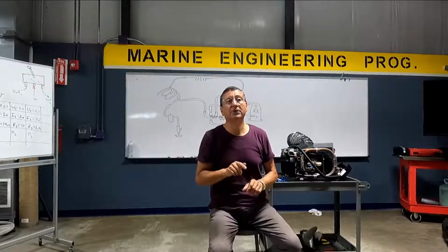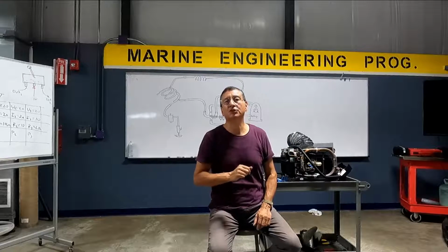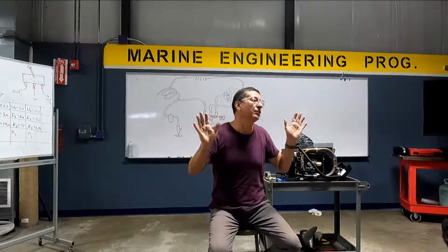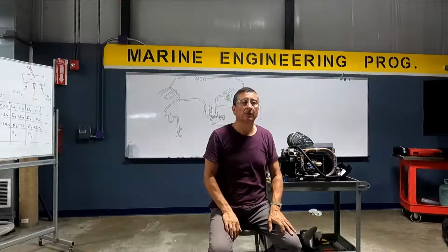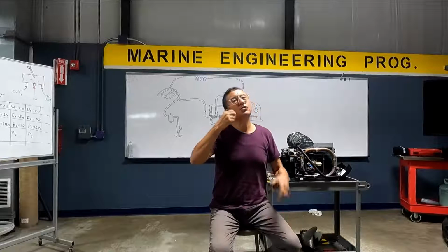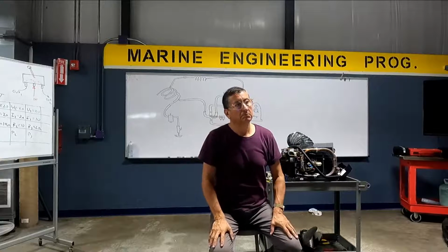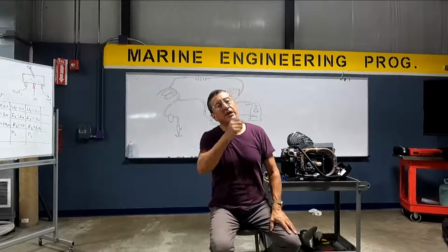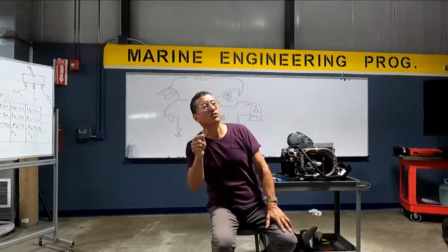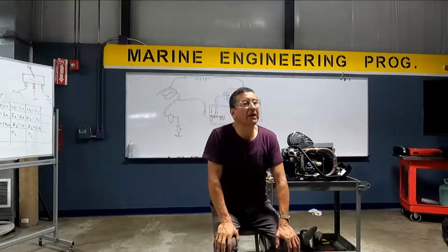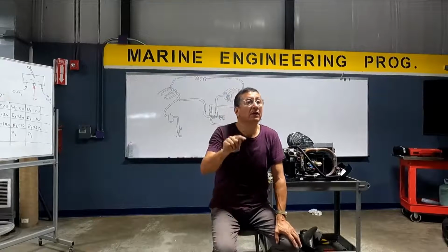High pressure and high temperature on the high pressure side. And what happens with the high pressure switch? It opens and turns off the compressor, because you have a lack of raw water. My air conditioning unit starts, works a couple of minutes, and stops suddenly. Excuse me, can you start the air conditioning unit again? And can you check the raw water outside of your boat? Oh, there is no raw water coming out. Okay, that's the problem.